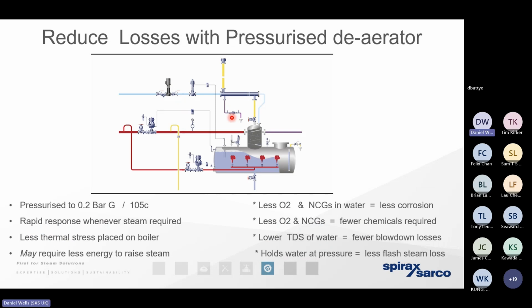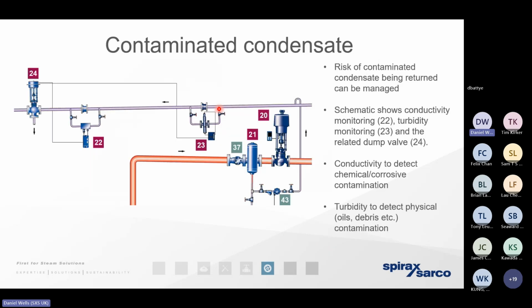Some processes, food, bev, pharmaceutical sector especially, they may elevate pressure and therefore the temperature of the water that's held in storage in what we call a pressurized deaerator. So if we can elevate that water that's in storage to 105 degrees, there's more energy in the water. Of course, we don't need to consume as much gas. We also don't need to consume as many chemicals. Therefore, we don't need to perform as much blowdown of the boiler. So the energy savings, the cost savings are coming to us from different directions. But it also means we've now got an excellent heat sink for all of those flash steam vents that were previously venting away to atmosphere. We can move one step closer towards a zero net loss steam system.